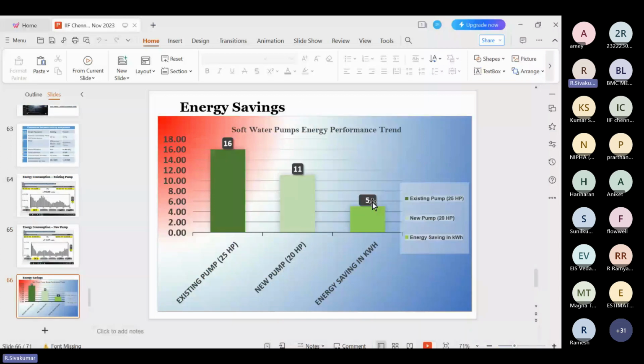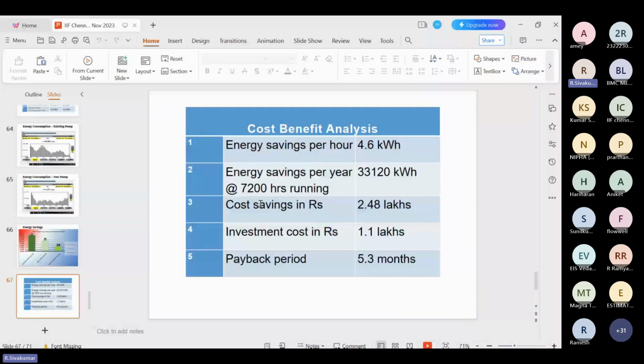So the annual saving at 7,200 hours is nearly 33,120 units. Cost saving is 2.48 lakhs in a year, and investment cost is 1.1 lakhs. The payback period is only 5.3 months. During this period, the average energy cost was around 7 rupees 30 paise. Now the energy cost is nearly 8.8 rupees per unit. So still this payback is short. Now it is implemented in the recent period, so the payback is less.